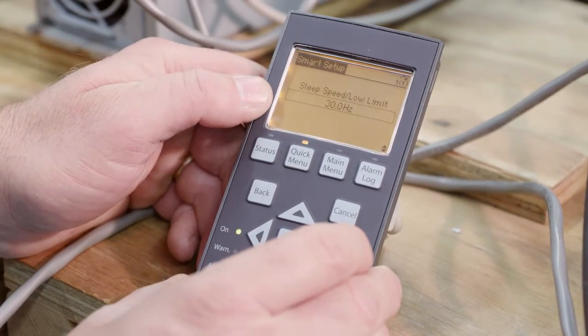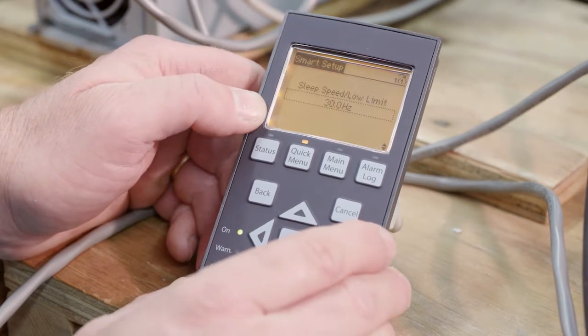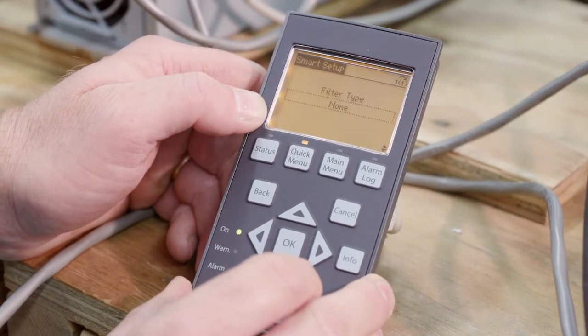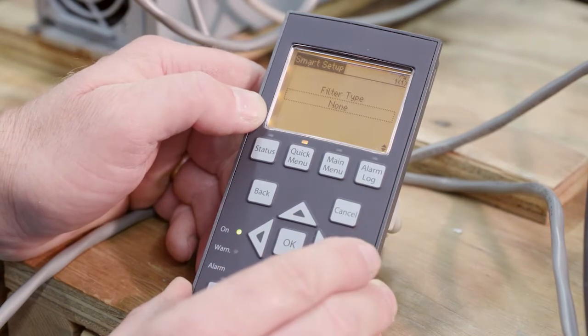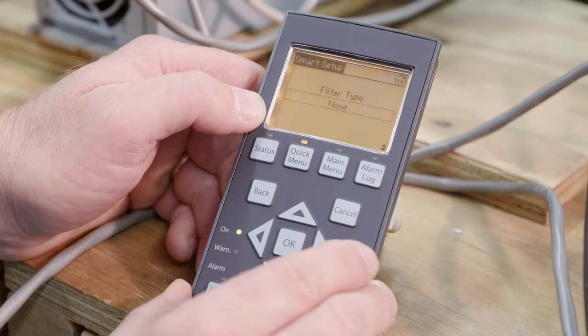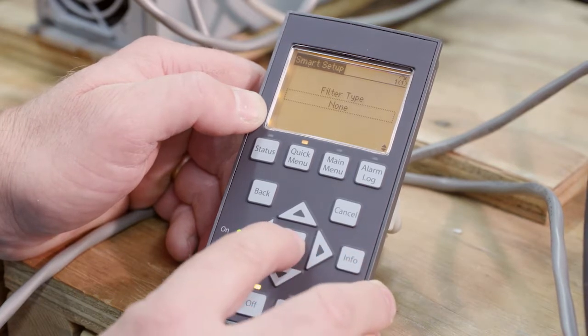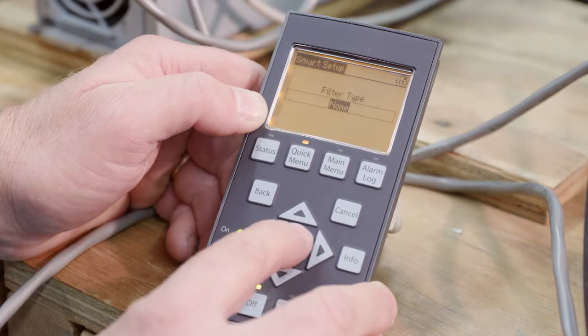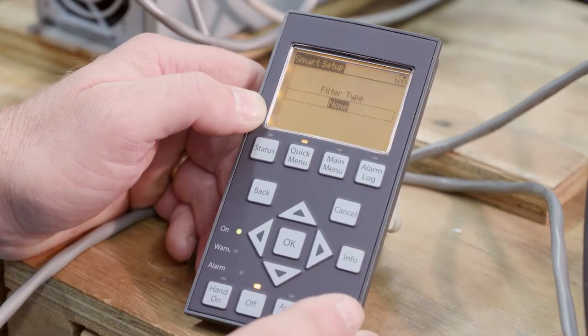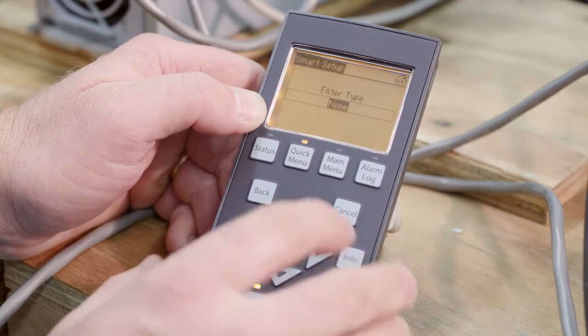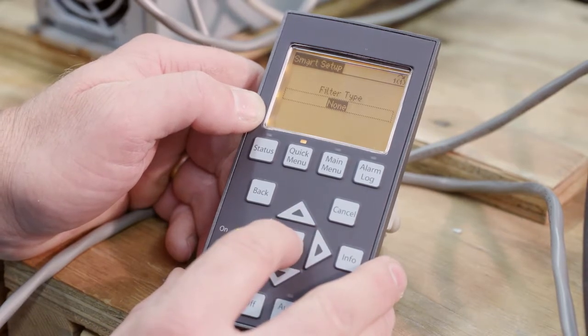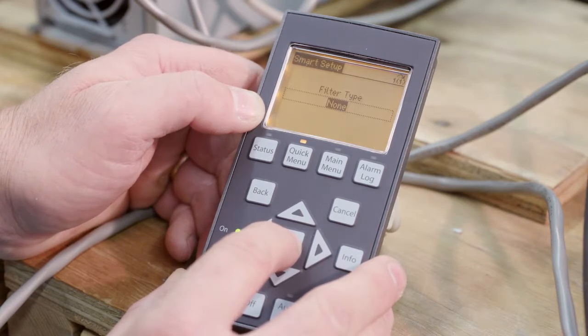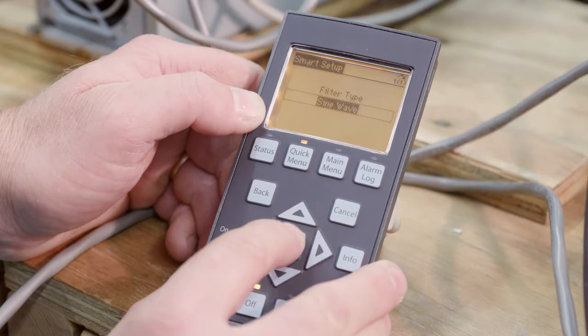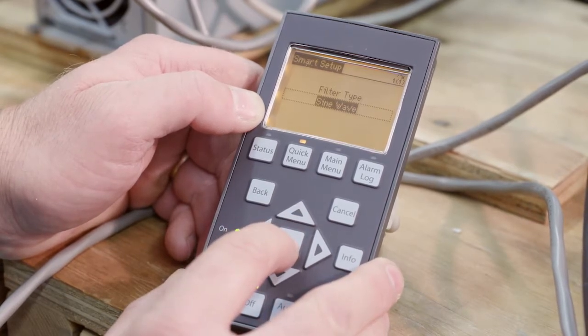Sleep speed, low limit of 30, which is where I'm going to leave that for this system, 30 hertz. One of the things that's new with the advanced is filter type, and what we're referring to here is the electrical output filter. Let's take a look at some of the options. In this case, we want none because our motor lead length is less than 50 feet, so I don't need an electrical output filter. But with other pumps, certainly submersible pumps that have long motor lead lengths, you're going to need to add a filter, and you get the option here to identify what type of filter you've added.